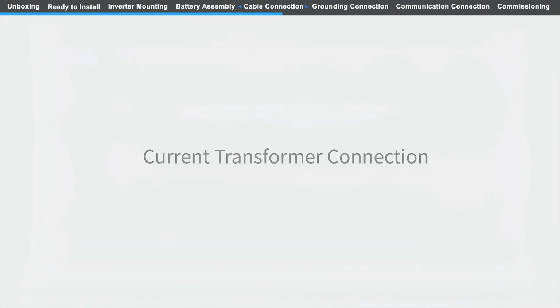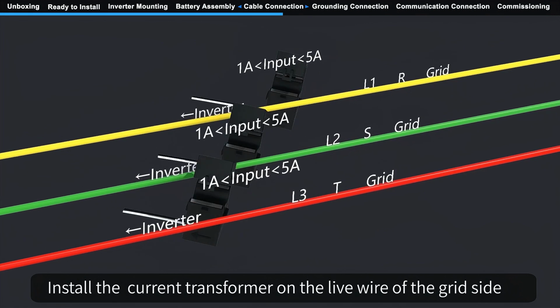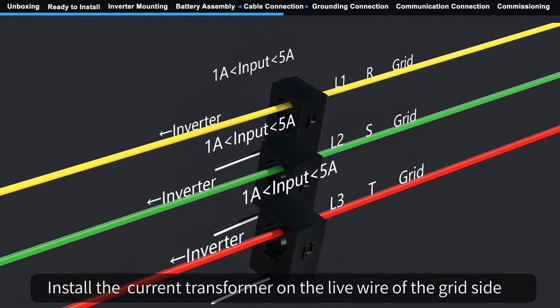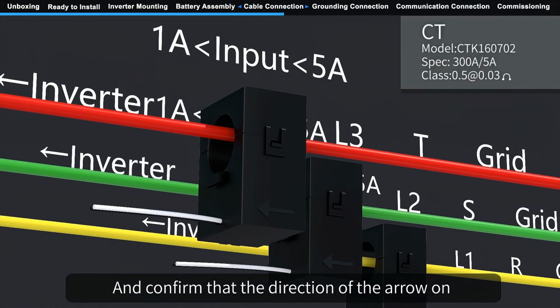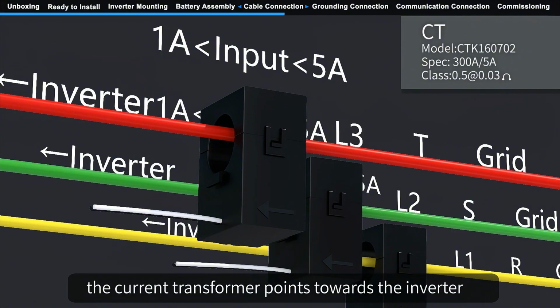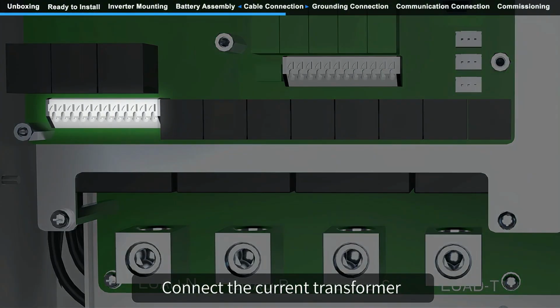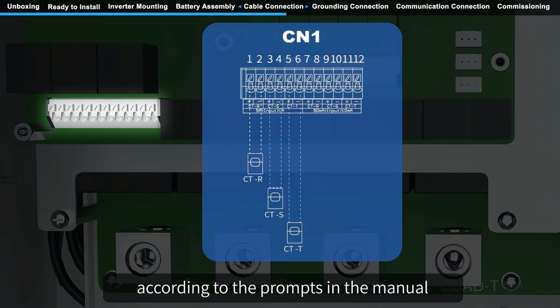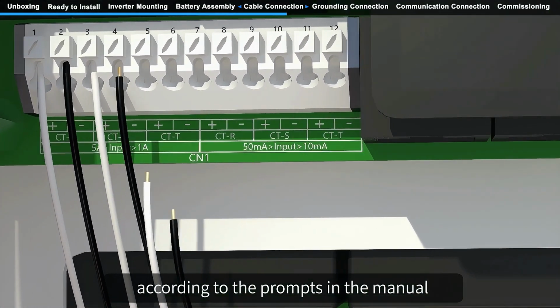Current transformer connection. Install the AC current transformer on the live wire of the grid side, and confirm that the direction of the arrow on the AC current transformer points towards the inverter. Connect the AC current transformer according to the prompts in the manual.